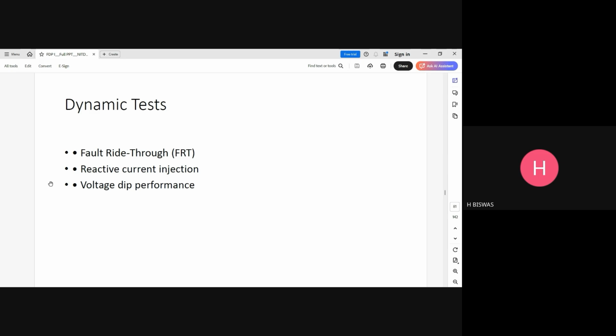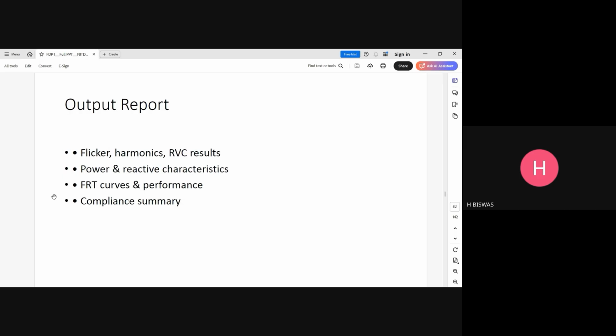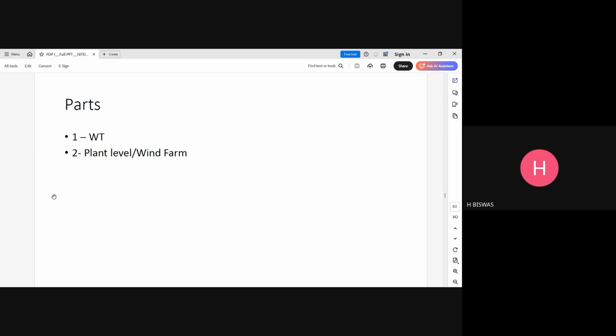Anyway, FRT, fault ride through, reactive current injection, voltage dip performance. So these dynamic tests are carried out. And the output report comes out with flicker, harmonics, RVC results, power reactive characteristics, FRT curves, performance, compliance summary, this kind of thing. Now, this has got two parts. One is for the individual wind turbine, and the second is for the plant level or wind farm, because a wind farm can comprise many wind turbines, not necessarily every turbine of the same capacity. That means you could have a wind farm that comprises different kinds of wind turbines altogether.